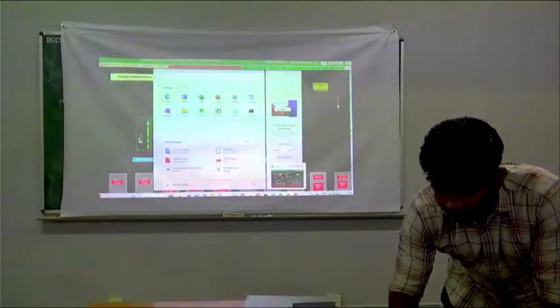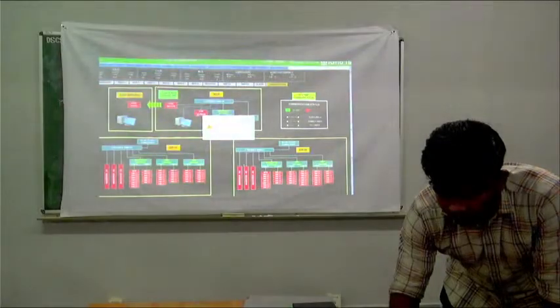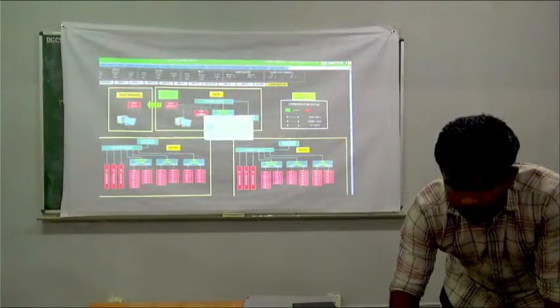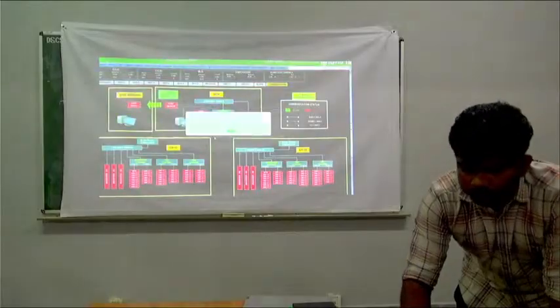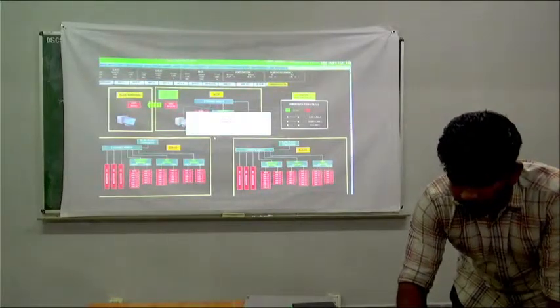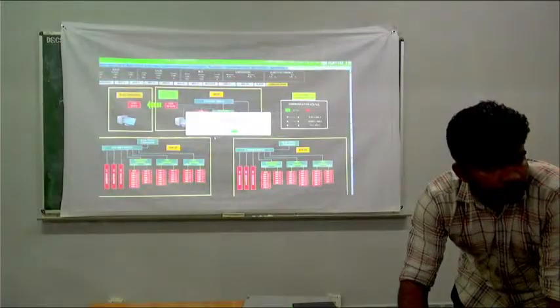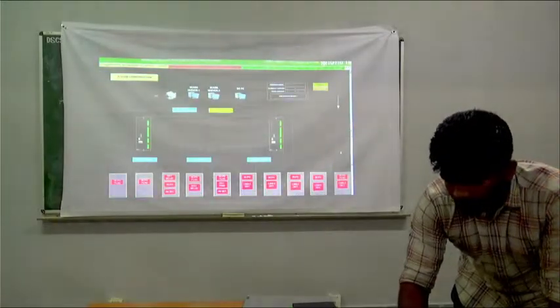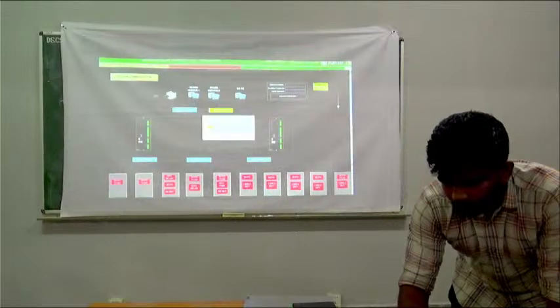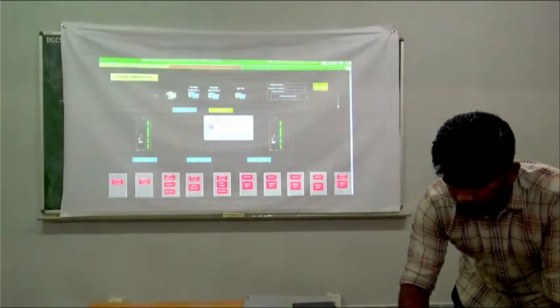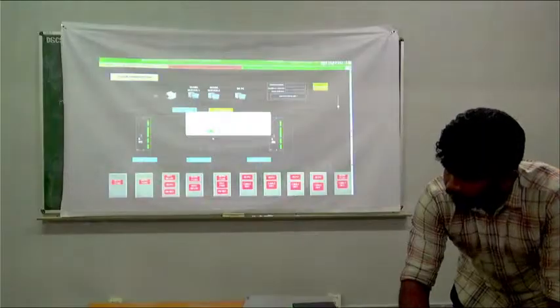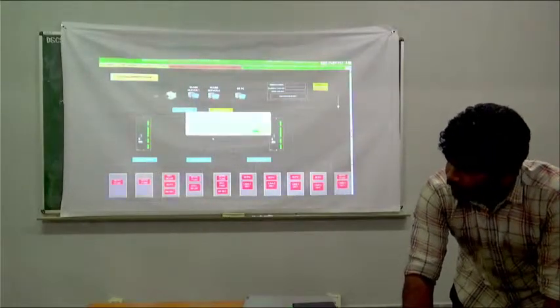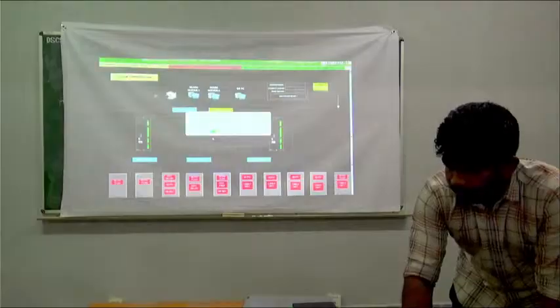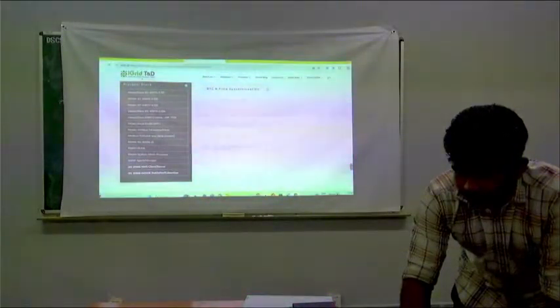Communicating with the meter - what we'll see is, we'll understand how we can read the data from the meter and see the live data. Practically, this is what we do in all substations, or any application for that matter. If you want to read some values, you usually read them using Modbus. Whenever I talk about any automation activity, the data will most of the time come in Modbus. From that Modbus, my gateway is able to read the data. I'll read the data in that gateway and show you the meter data coming in. The same thing we can also show in our SCADA.